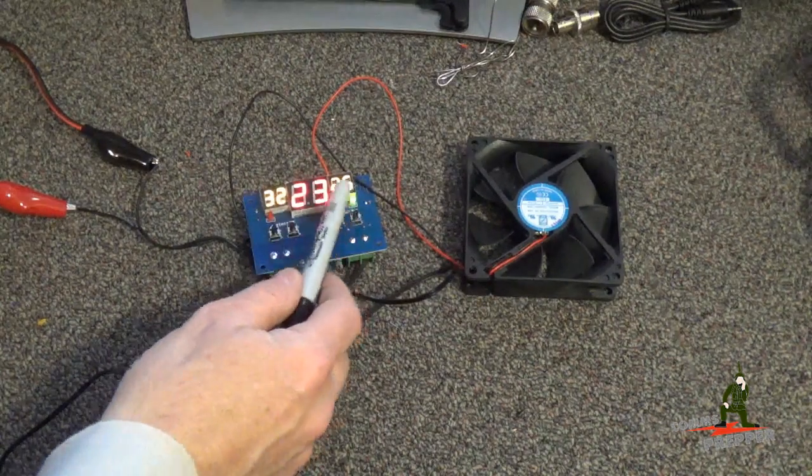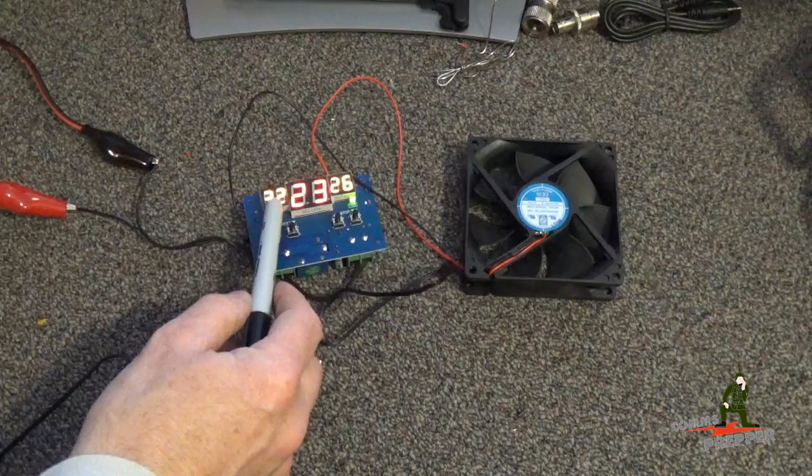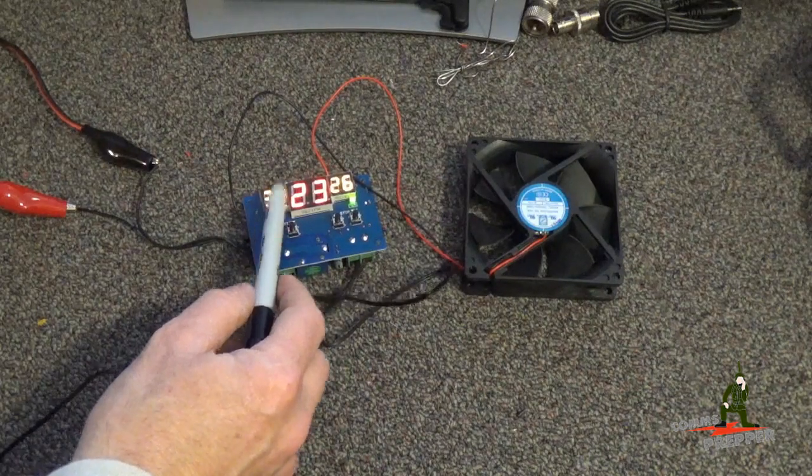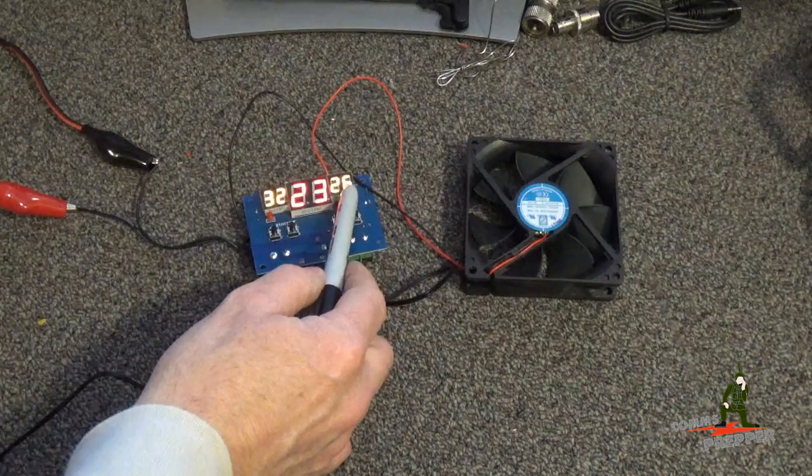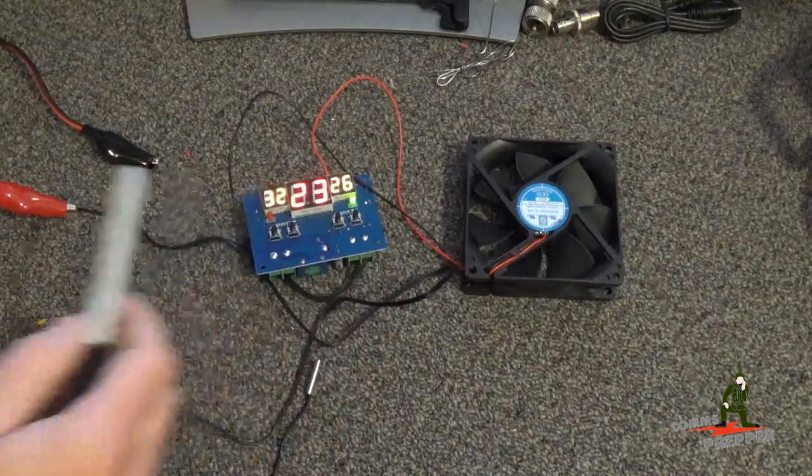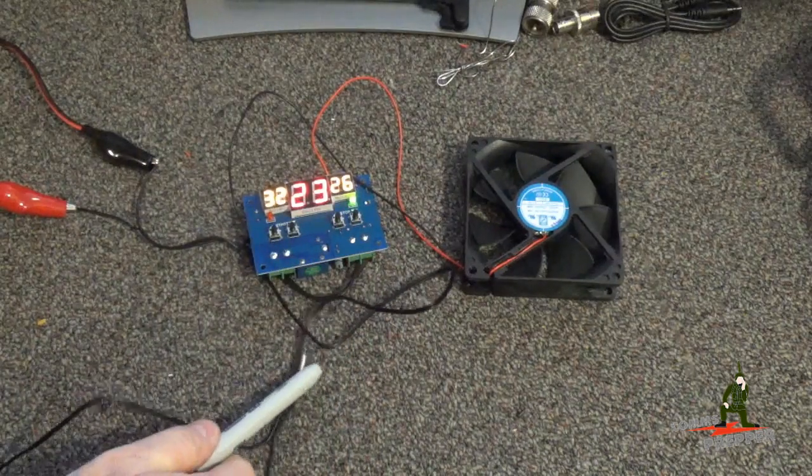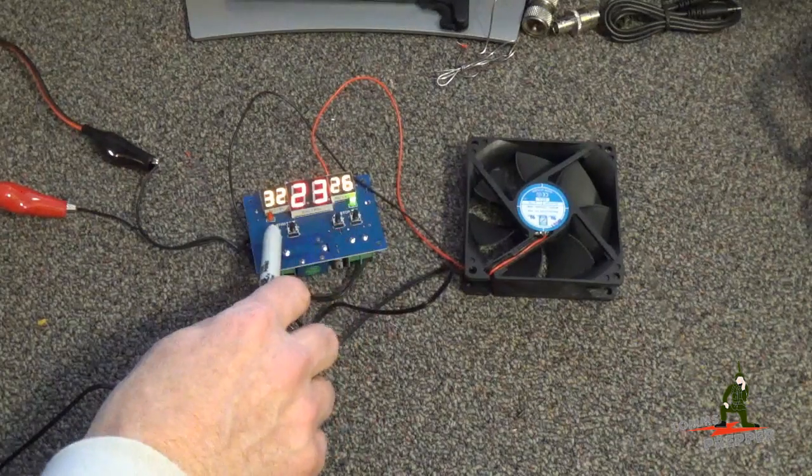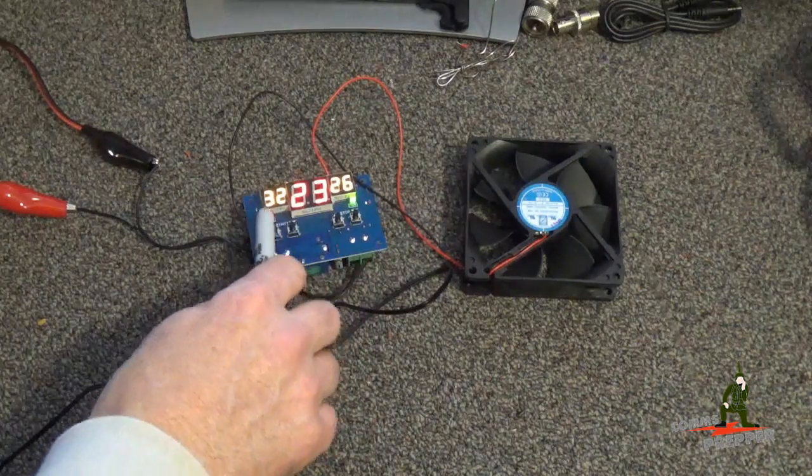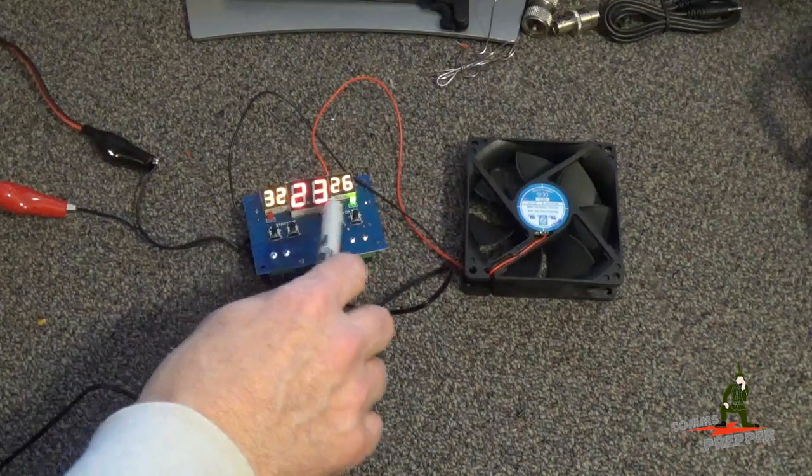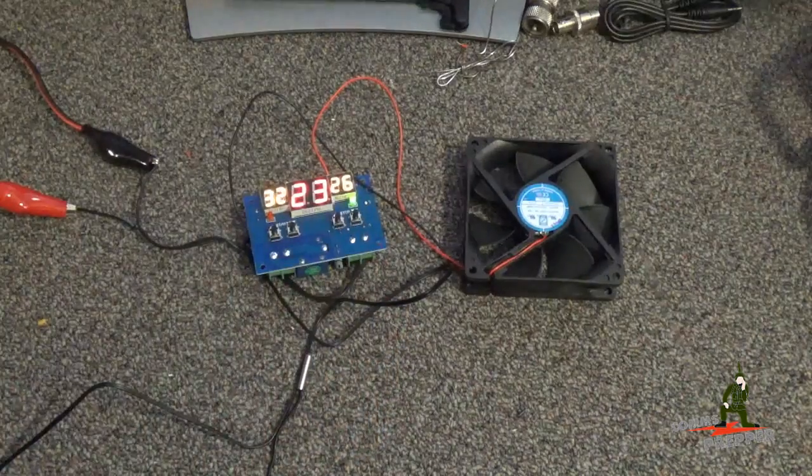The card only comes for Celsius, so that's why these numbers are here. This is 32 degrees Celsius to turn the fan on, 26 degrees Celsius to turn the fan off, and in the center is the actual temperature that this sensor here is picking up. You've got four buttons here, up and down to set the temperature turn on, and up and down to set the temperature turn off.